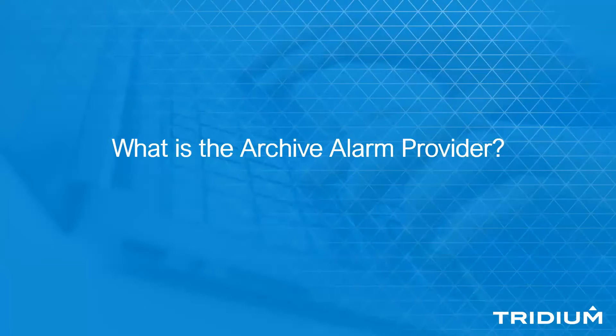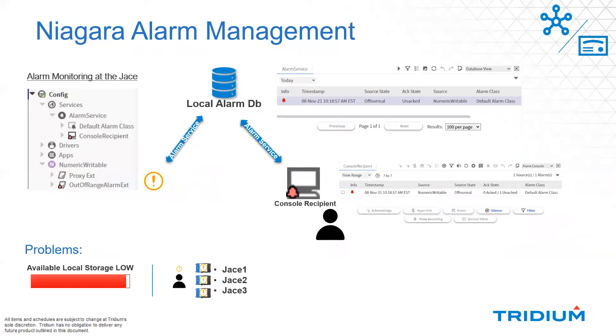So what is the archive alarm provider? I'd like to take a step back and review how we do alarm management and how the alarm space works in Niagara. Starting at the top left, here's a small snapshot of a station running on a JACE. You simply could have any kind of numeric writable and you add an alarm extension to it. It's the alarm extension that's monitoring the condition you're wanting to alert the user to. Once that condition is met, it's the alarm service that generates this alarm record and accesses the local alarm database in the station. This is a native Niagara alarm database.